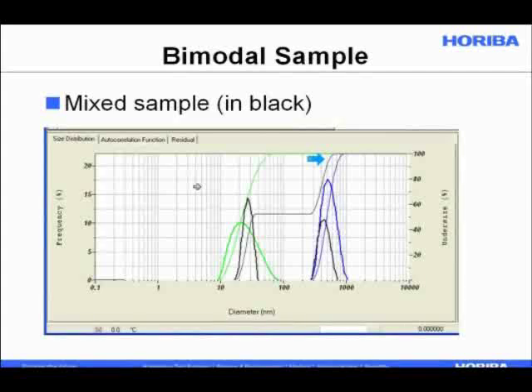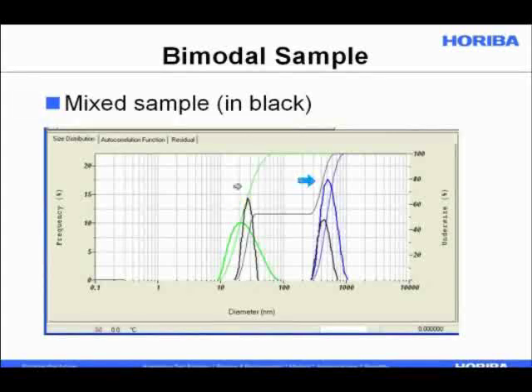For multimodal size distribution analysis, peaks generally need to be spaced fairly far apart, and the scattered intensities from each population should be within the same order of magnitude. This is not routine quality control analysis — it requires expert interpretation. But for formulation work, if you consistently see two peaks when you expected one, that's very valuable information to guide your recipe or manufacturing scheme. This kind of analysis belongs more to the R&D lab than the quality control environment.